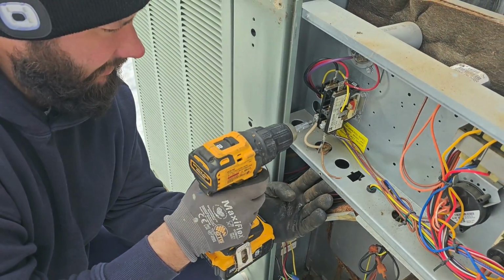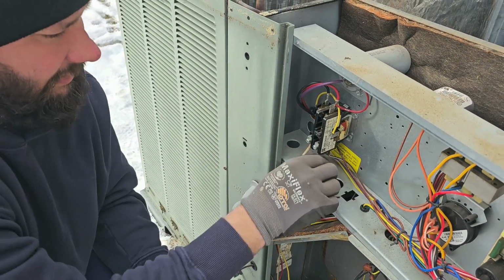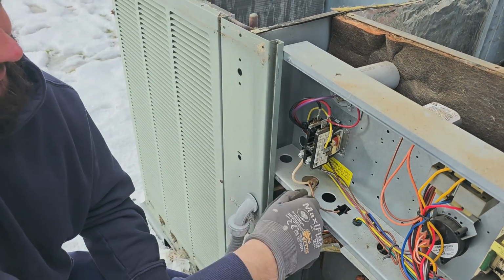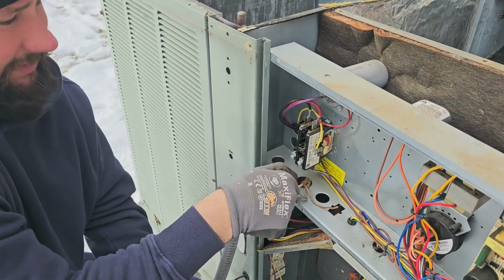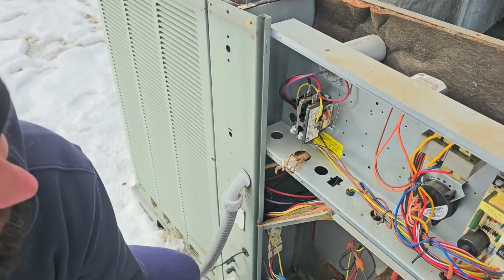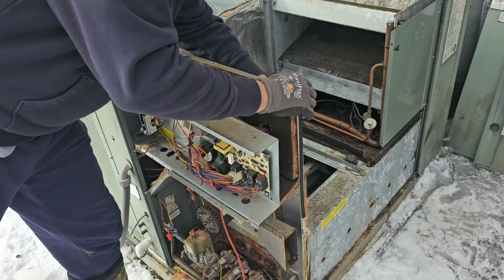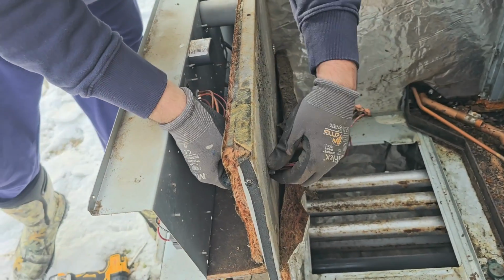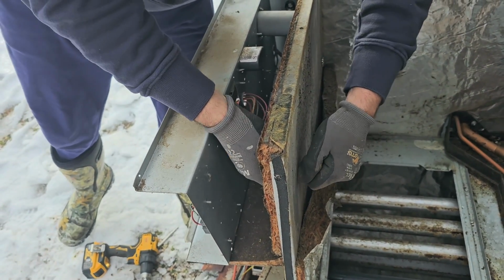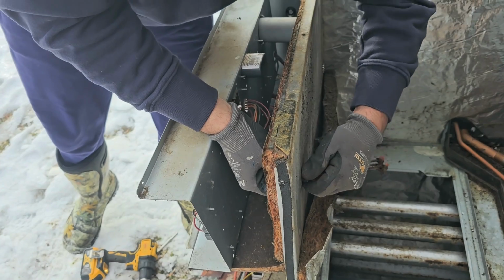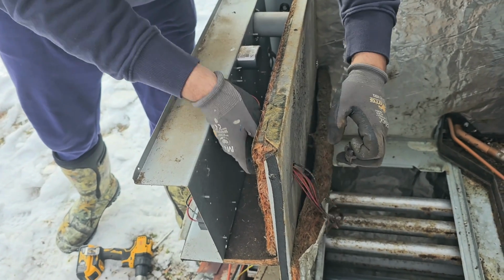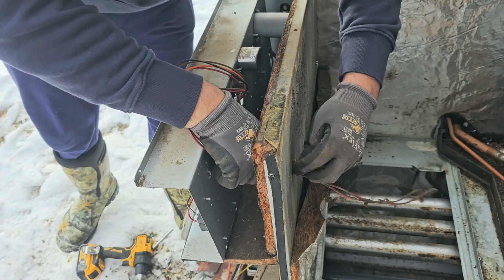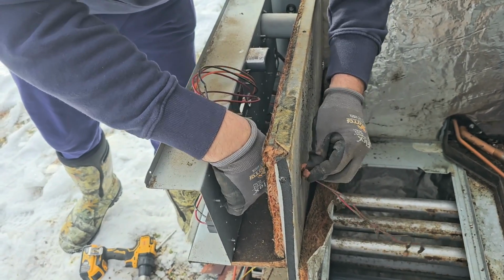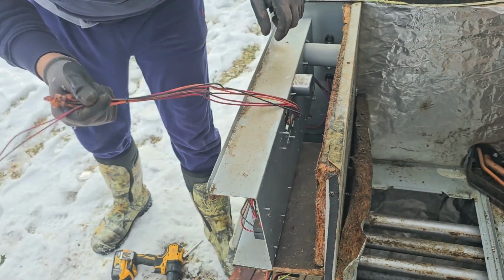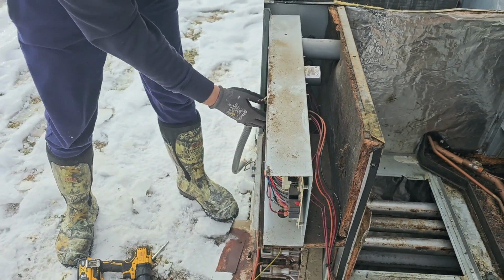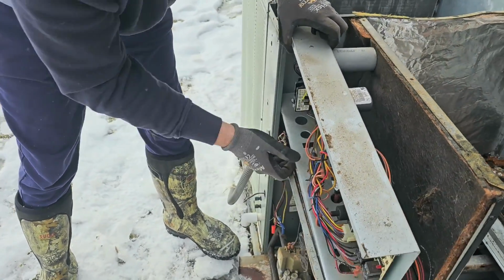Now we need to take the power that comes into the contactor loose so that we can get this panel out of here. The wires that went to the indoor fan motor need to be pulled out, because we can't keep them in and try to take the heat exchanger out. Make sure you know how to read a schematic. If you do, you don't have to worry about what wire goes where, because you know what you're doing. If you don't, I've got a bunch of videos on reading schematics. I encourage you to go check those out.